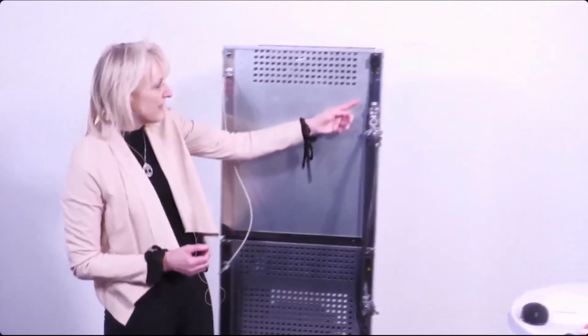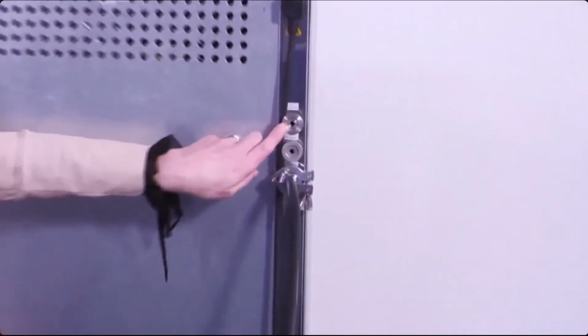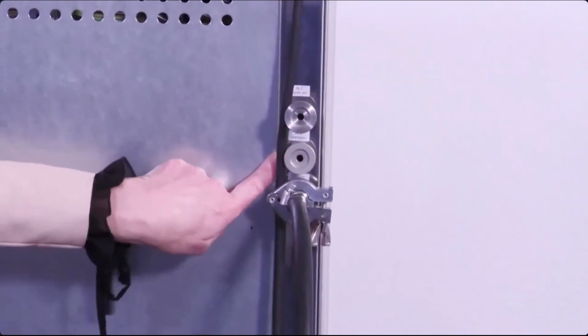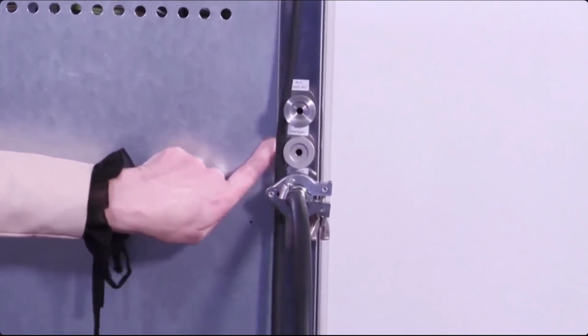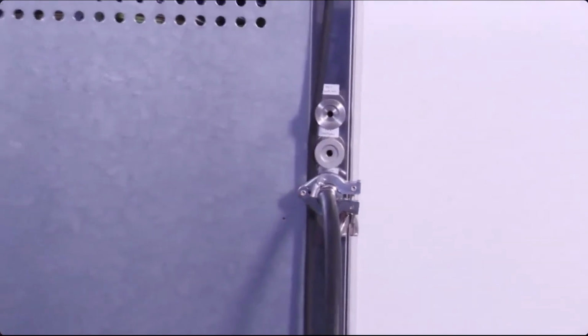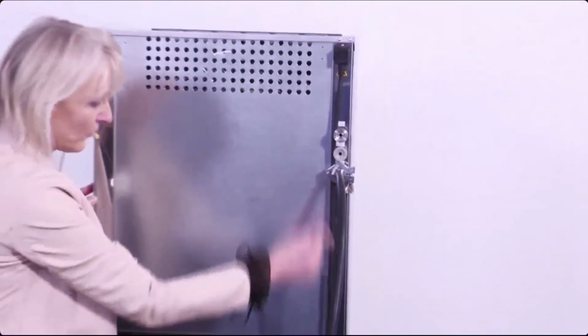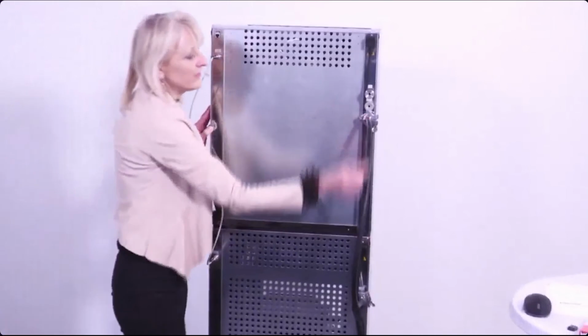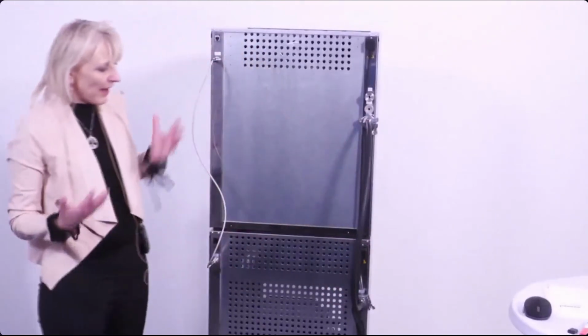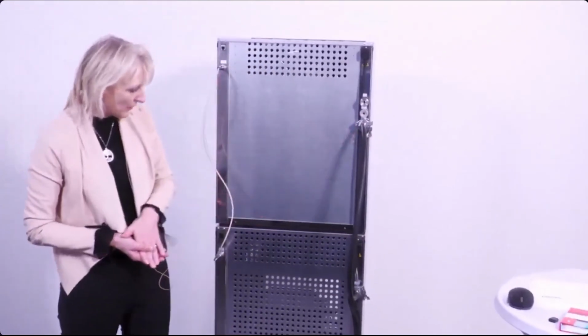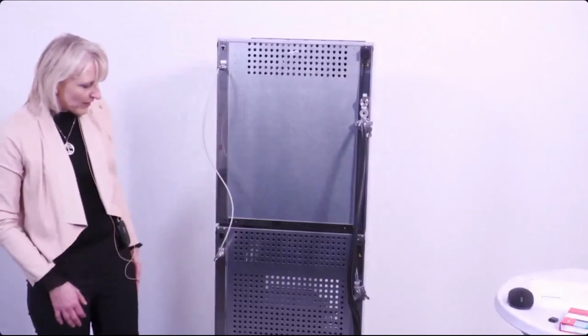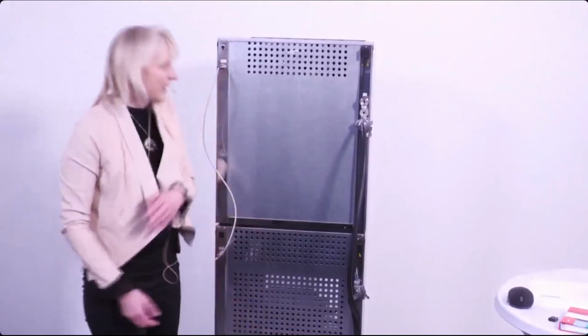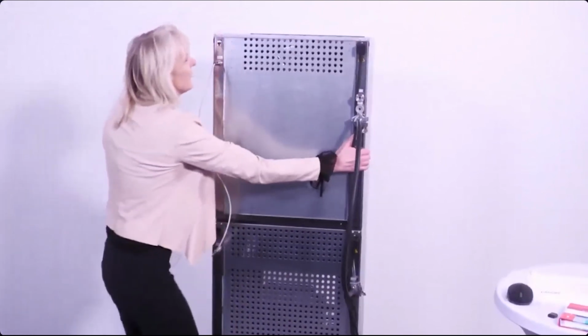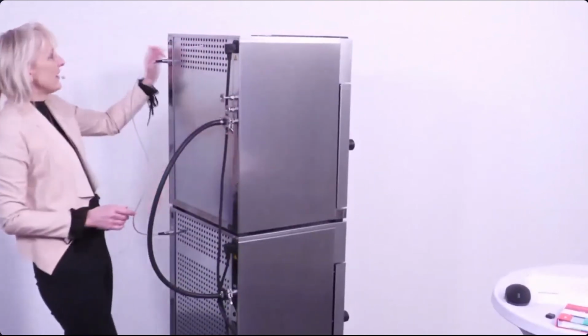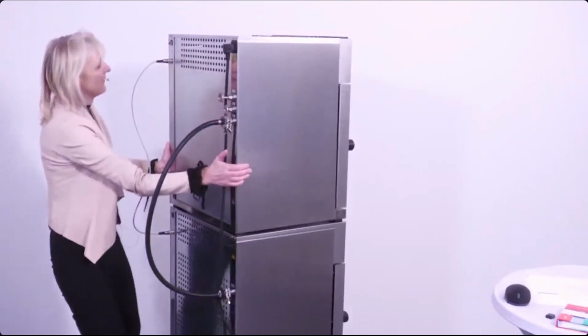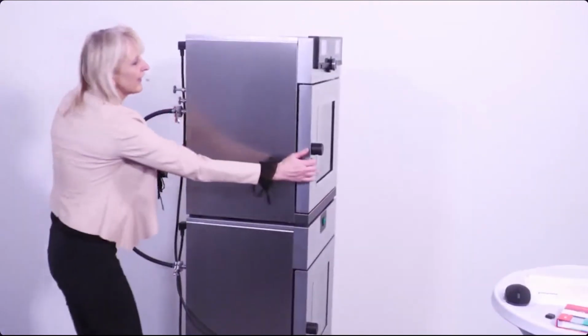On the other side, we see here a connection for air and also for inert gas. So here you can operate with inert gas. That means we have here the premium module. And here we have the connection to the pump. So it's the tubing for the pump connection with the housing. And in case you want to have an exhaust, it can also be connected. That was all with regard to the vacuum oven. That is also the interface, not to forget. So we have an Ethernet interface for the vacuum oven.